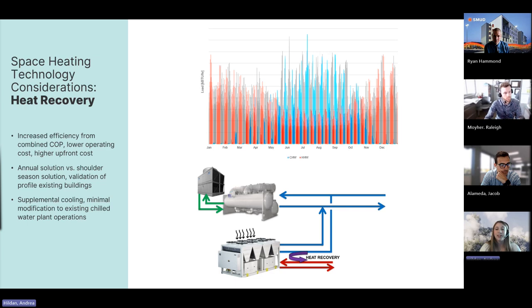There's opportunities to introduce false cooling loads to help the building have more simultaneous loads. And then there's some unique applications where you're actually able to recapture rejected heat and repath it into an alternative system. On the next slide, Jacob's going to touch on this with domestic hot water and specifically hybrid heat pump water heaters.